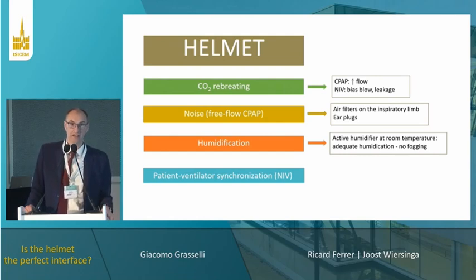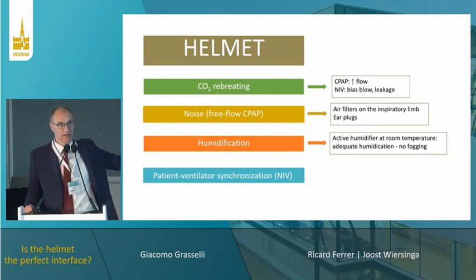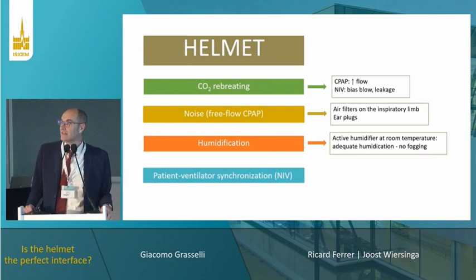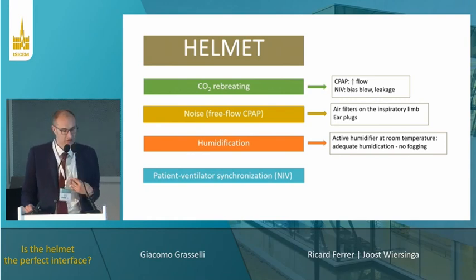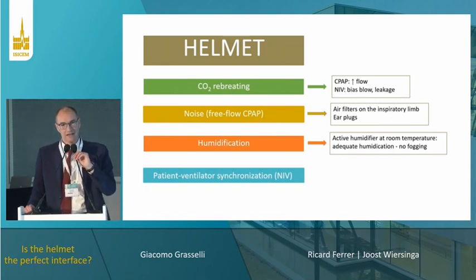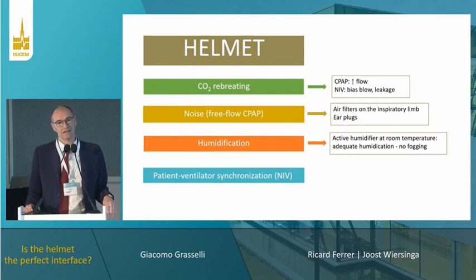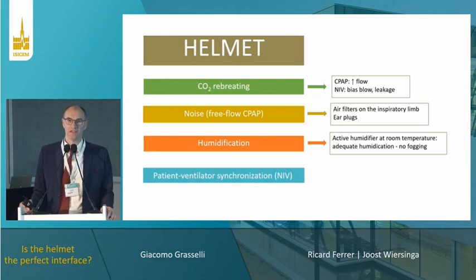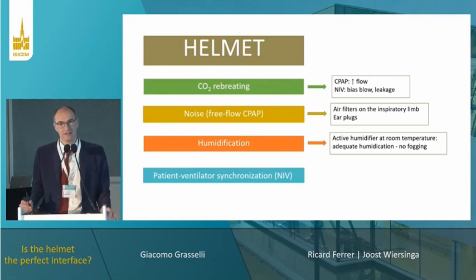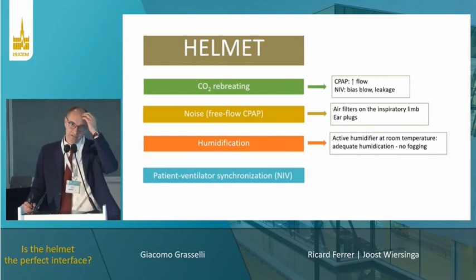Another problem is humidification, because as you know, the air that comes from the wall is dry, and it's very unpleasant to breathe dry air. But you can humidify the helmet, even with active humidification. Clearly, you need to keep, for example, the temperature very low in order to avoid fogging. But with the new humidifiers, you can do it. And then there is the issue of patient-ventilator synchronization.